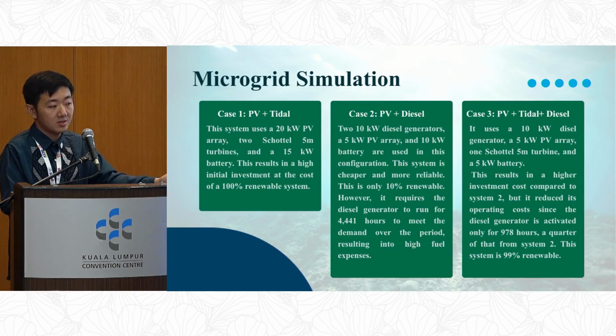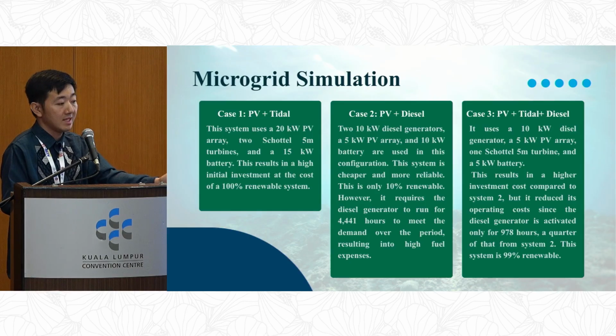For case 3, we used PV plus tidal plus diesel: a 10 kilowatt diesel generator, 5 kilowatt PV array, one 5-meter tidal turbine, and a 5 kilowatt battery, with the diesel generator used only as backup. This has a bit higher investment than System 2, but reduces operating cost since it only requires 978 hours, just a quarter, and this energy mix is 99% renewable.